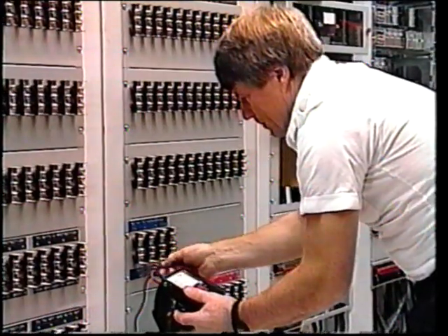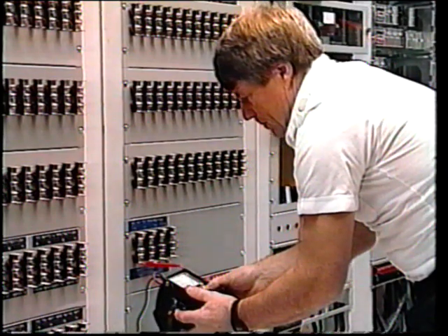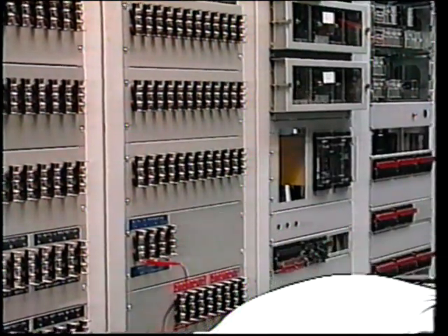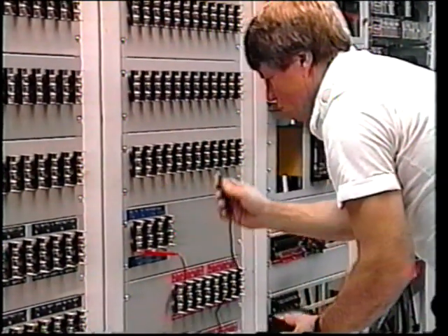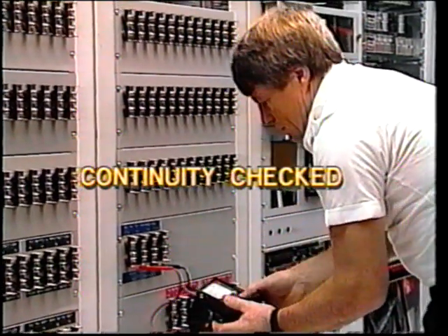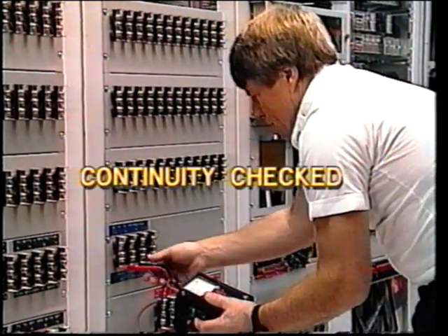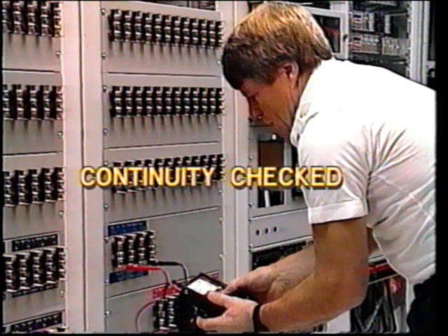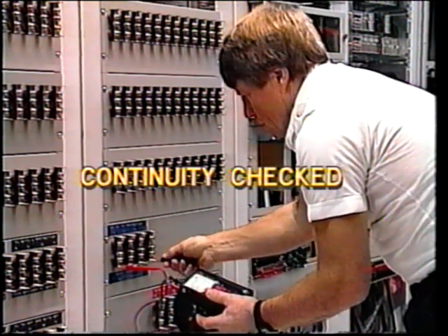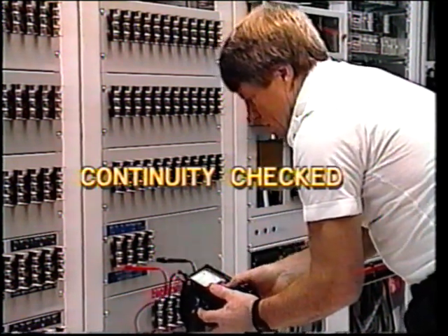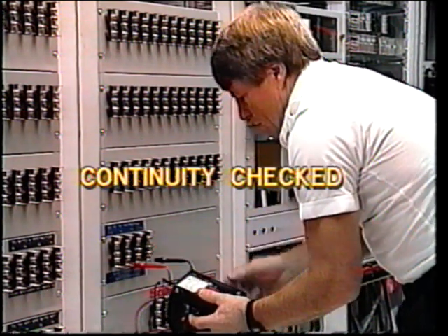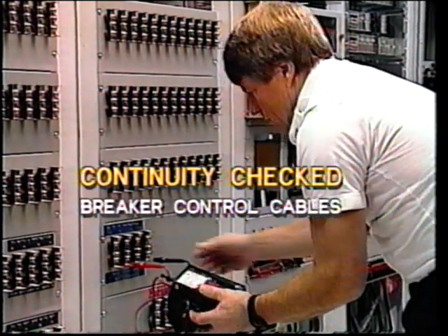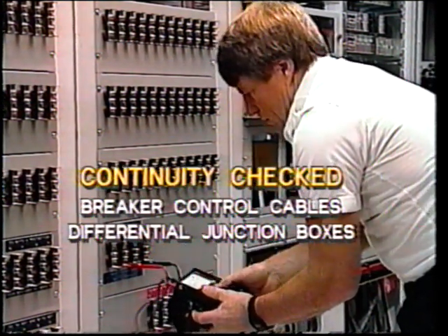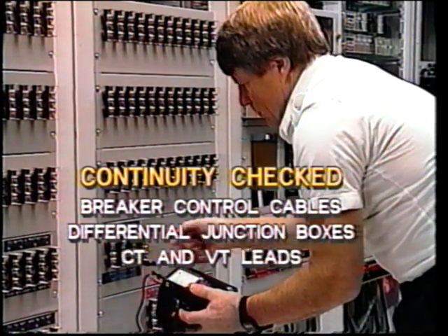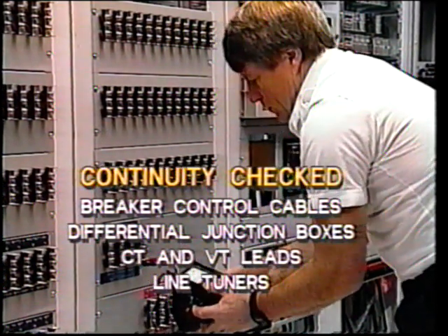On new installations, all of the wiring must be checked to see that it conforms with the diagrams. Point-to-point continuity and insulation integrity must be checked on all AC wiring, from switchyard terminal blocks to the termination points in the control panel. Typically, this will include breaker control cables, differential junction boxes, CT and VT leads, line tuners, and so on.